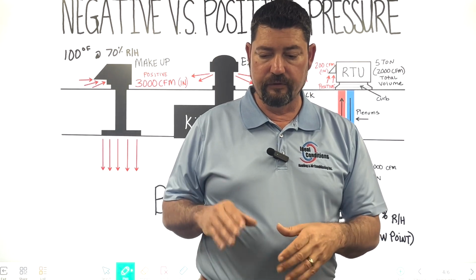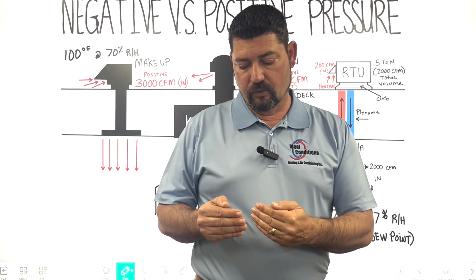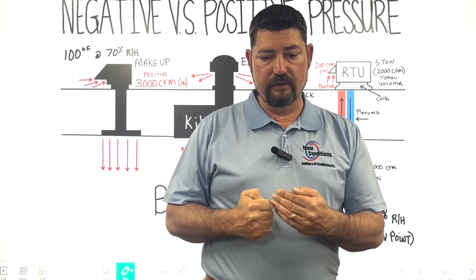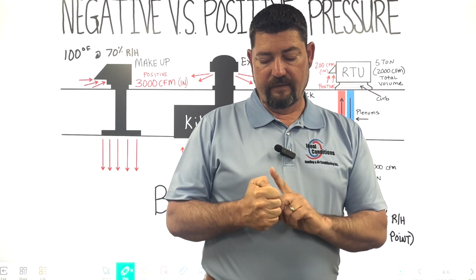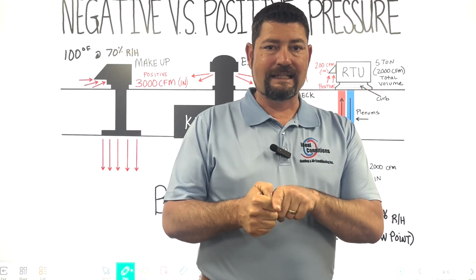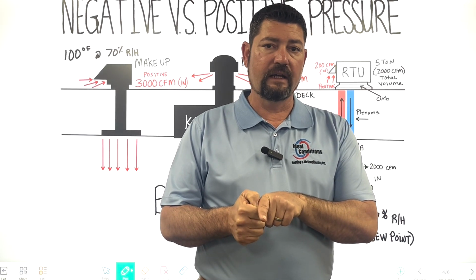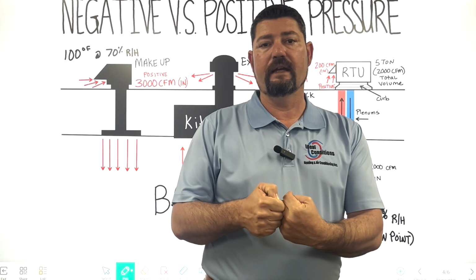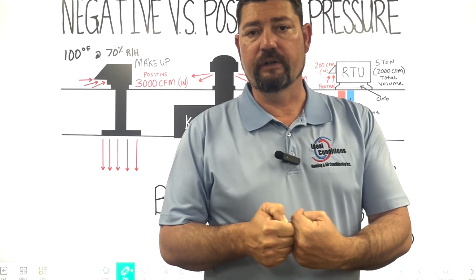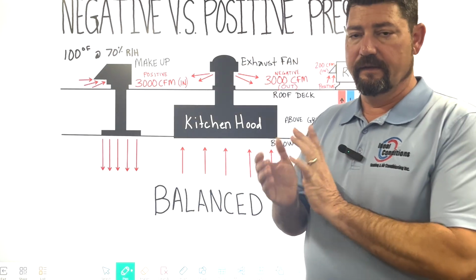If all the doors are closed, front and back, open up the front door just a little bit, and you can just take a lighter and light it. If the flame points inside the building, then you have a negative pressure. If the flame points outside the building, then you have a positive pressure. If the flame points straight up, then you're balanced.